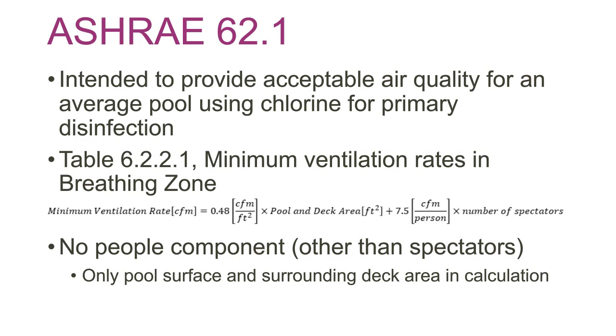In the case of pools, it is strictly an area rate, and basically what it's telling you is, to the breathing zone, which is 6 feet above the floor, you need to get 0.48 CFM per square foot of pool and deck area. If you have a spectator space, that falls under a different occupancy category, and you have to have 7.5 CFM per spectator, and that's only needed when that area is occupied. It's worth noting that there's not a people component to that. Most other spaces in 62.1 have both a base area component and a component for people. But in the case of the pool, it's really only the pool surface and the deck area that's used in the calculation, and the people component is really for indoor air quality, for chloramine removal.